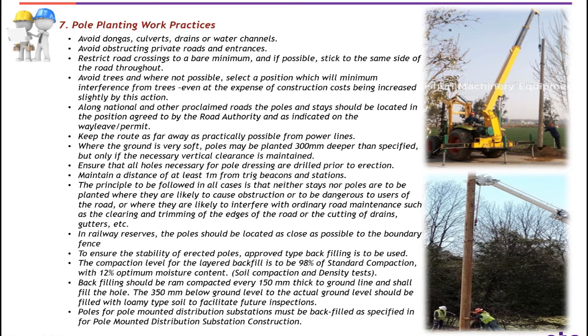Number thirteen: backfilling should be rammed and compacted every 150 mm thick to ground line and shall fill the hole. The 350 mm below ground level to the actual ground level should be filled with loamy type soil to facilitate future inspection. Number fourteen: poles for pole-mounted distribution substations must be backfilled as specified for pole-mounted distribution substation construction.